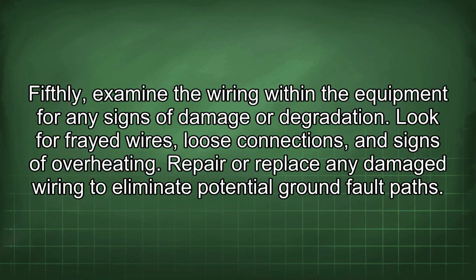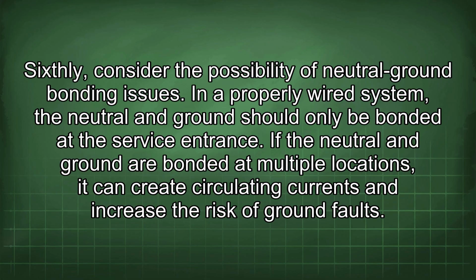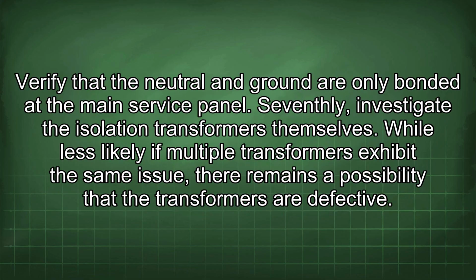Fifthly, examine the wiring within the equipment for any signs of damage or degradation. Look for frayed wires, loose connections, and signs of overheating. Repair or replace any damaged wiring to eliminate potential ground fault paths. Sixthly, consider the possibility of neutral ground bonding issues. In a properly wired system, the neutral and ground should only be bonded at the service entrance. If the neutral and ground are bonded at multiple locations, it can create circulating currents and increase the risk of ground faults. Verify that the neutral and ground are only bonded at the main service panel.